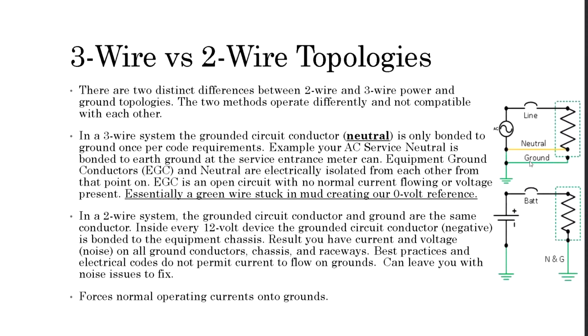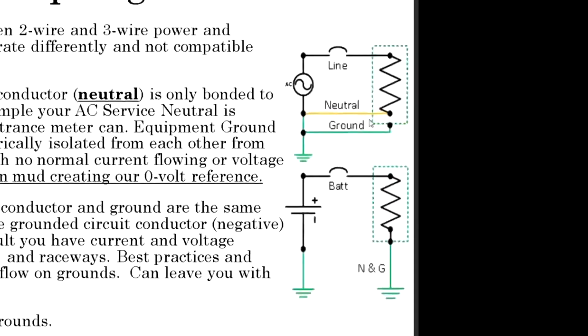Now, if you look over here on the right, we can see the line conductor. It goes to the load device. The load device is represented by our resistor here, and all the current returns on the neutral. Back here at our service, or wherever the source of the power is, the neutral is bonded to ground, and then they're kept electrically isolated. This chassis and the ground are completely an open circuit. There's no normal operating current.